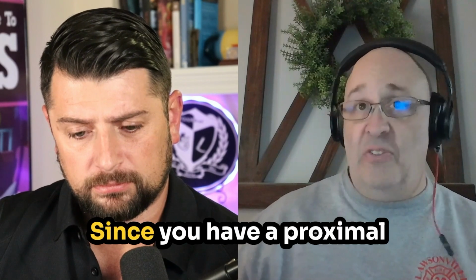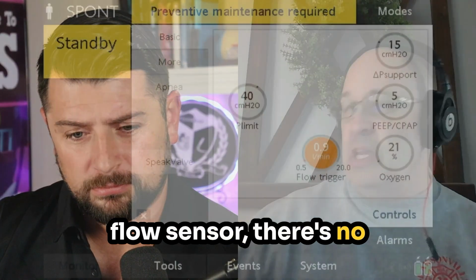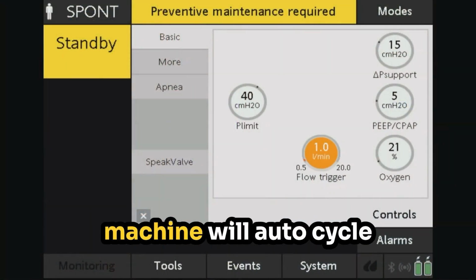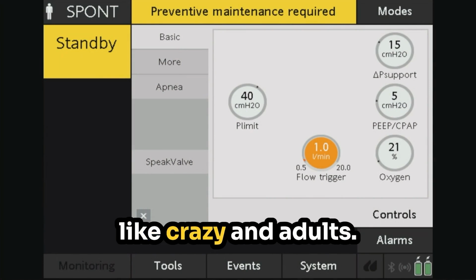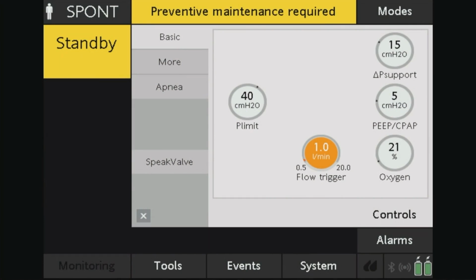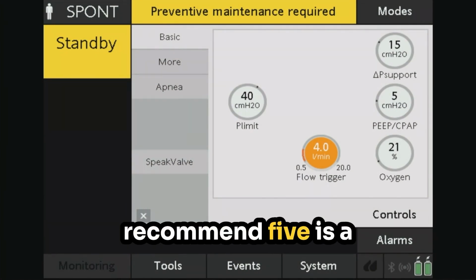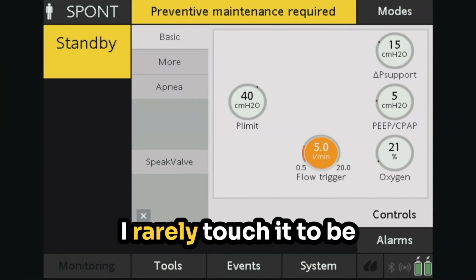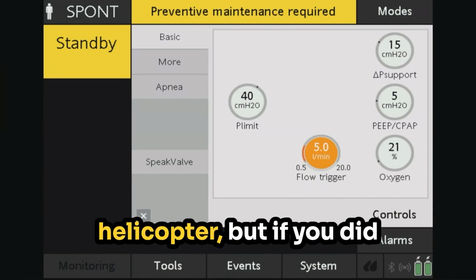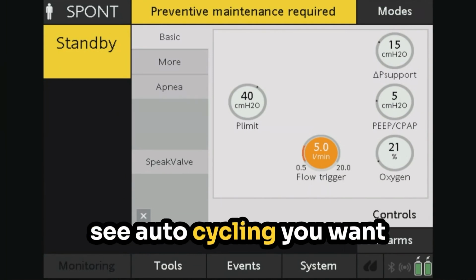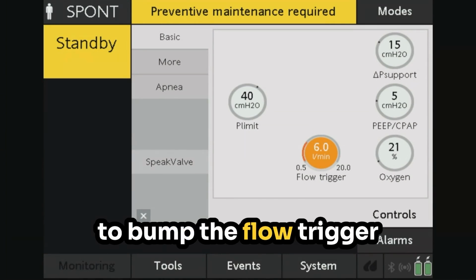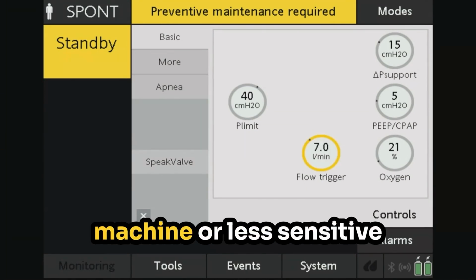With the Hamilton, since you have a proximal flow sensor, there's no need to put your flow trigger this low. Your machine will auto cycle like crazy in adults with it that low. And that's why we recommend 5 is a good place to start. I rarely touch it, to be honest, even on the helicopter. But if you did see auto cycling, you want to bump up the flow trigger. That's going to make the machine less sensitive to patient efforts.